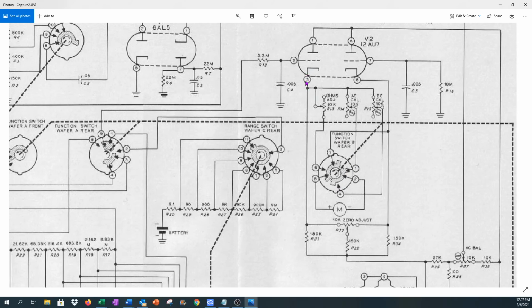Basically, we tie our cathode in. We're in AC mode, so we're going to be going through this AC calibration pot right here, and we're going to tie it in right here. It's going to go through the meter, out of the meter, pin 5, pin 7, and we're going to tie right back to this cathode. So as long as these cathodes are at the same potential, and this one's being held at a certain bias, so there's a certain current flow through this. Once we balance that out through this zero adjust and through our balancing, which we're going to do in the calibration procedures, there shouldn't be any voltage potential difference between this cathode and this cathode. Therefore, there won't be any current flow through this meter.